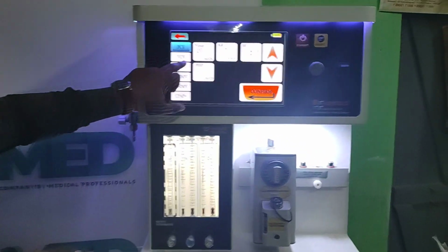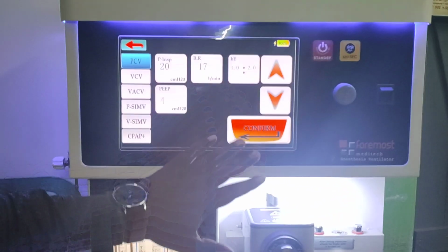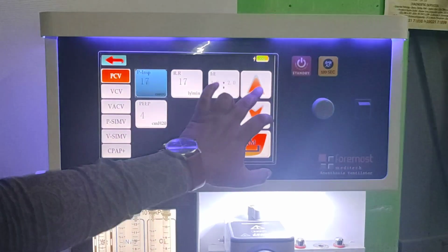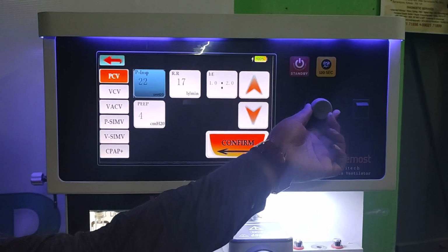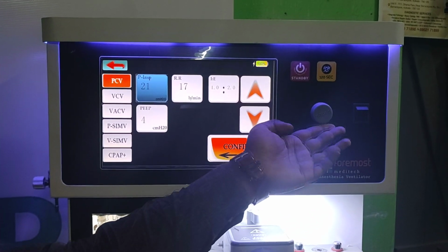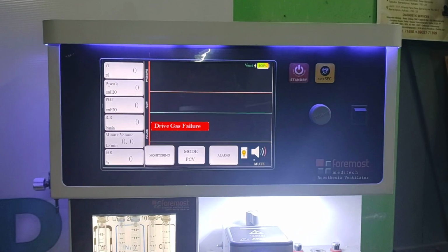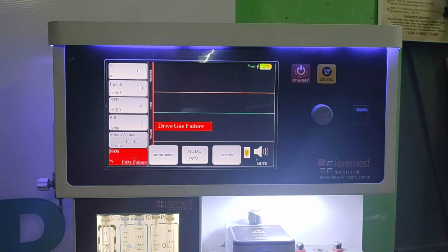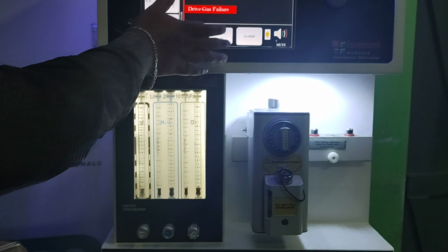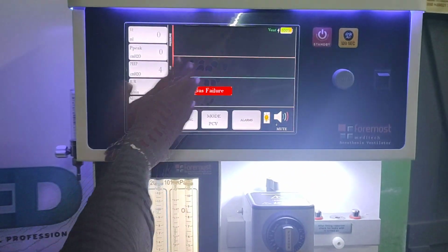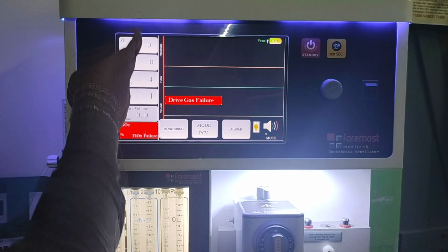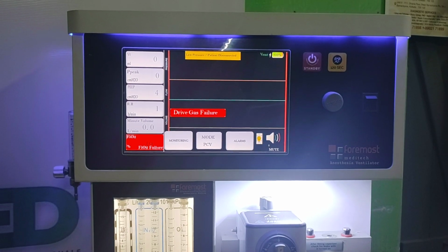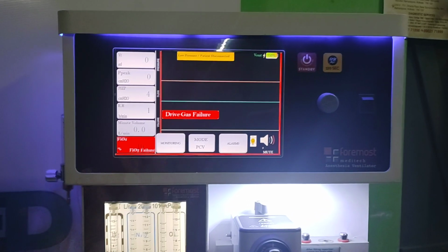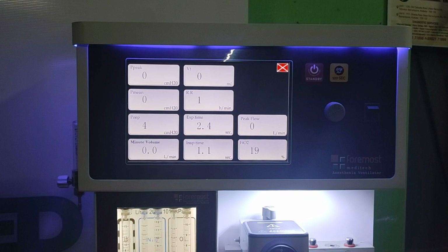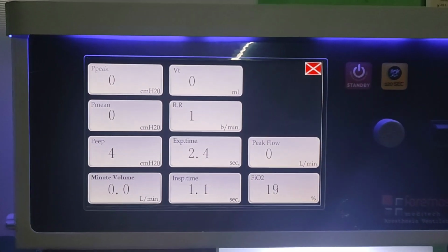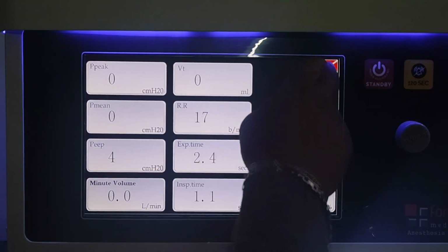Whatever mode you select, all parameters are here. You can choose and scroll the parameters. You can use this knob to scroll, and also you can touch here. When you confirm, it will start the ventilation, and the screen will show you the three graphs: pressure, volume, flow, and the patient parameters. Also, if you need to watch all the patient parameters, you can go to monitoring, and it will give you the data of the parameters the patient is receiving.